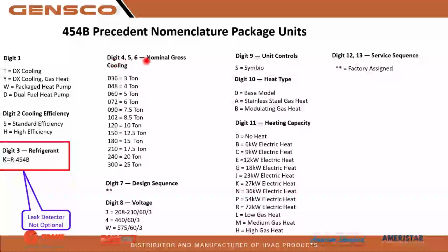Of course, your digit 4, 5, and 6 will be your tonnage. Here's a good, easy chart to refer to. Design sequence on number 7, your digit 8 is the voltage. Again, we have to pay attention to what voltage we have for the units because we're going to be setting those up, and you're going to have to set up the board if you replace a circuit board.